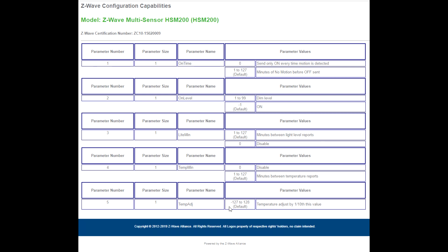And the range of allowed values are between minus 127 and plus 128. Now, those values are 10 times larger than the actual temperature you're adjusting. So in reality, this minus 127 represents minus 12.7 degrees, plus is 12.8 degrees. So you've got a range of minus 12.7 to plus 12.8 degrees that you can calibrate.